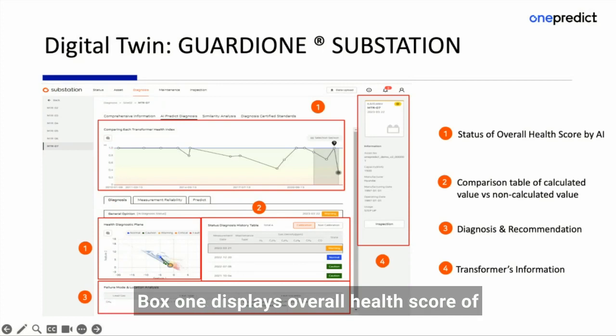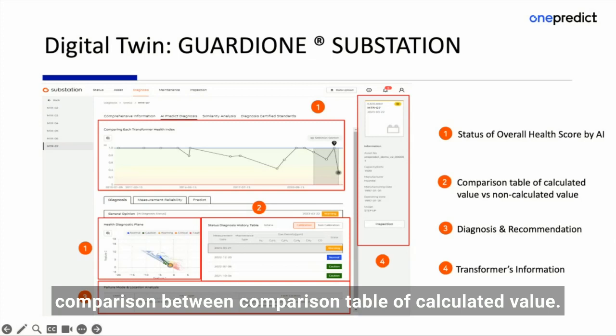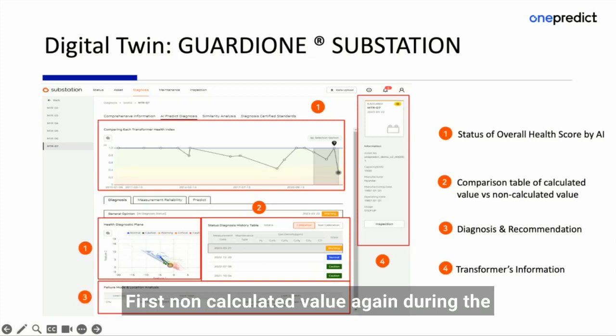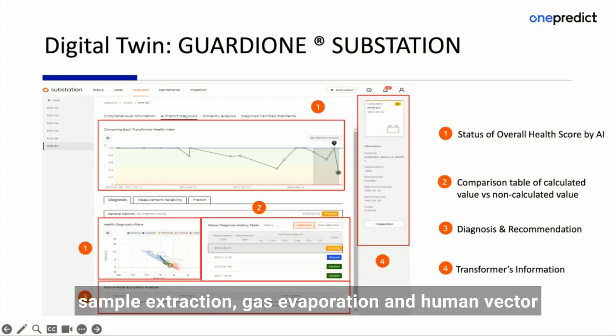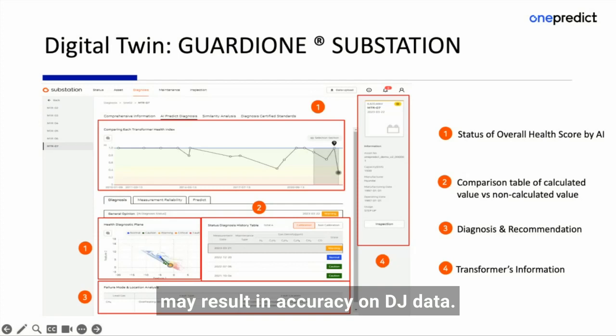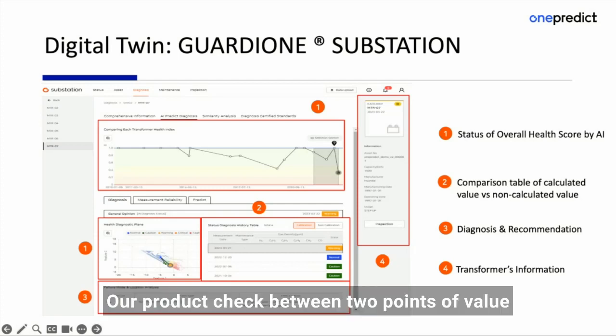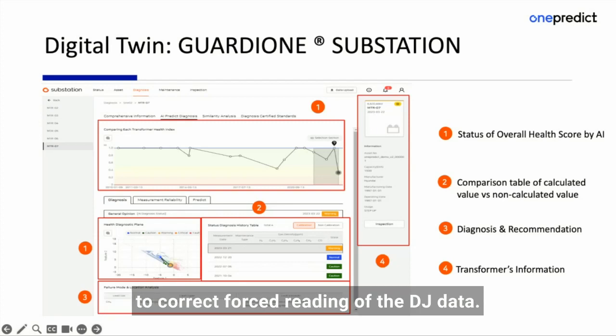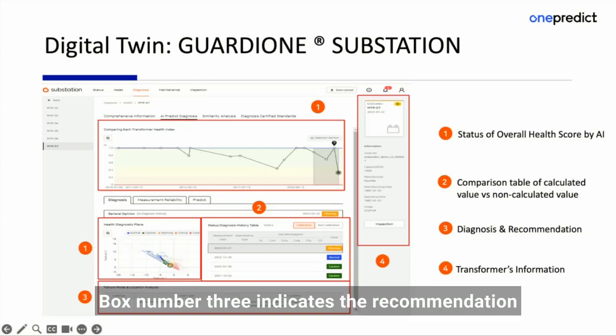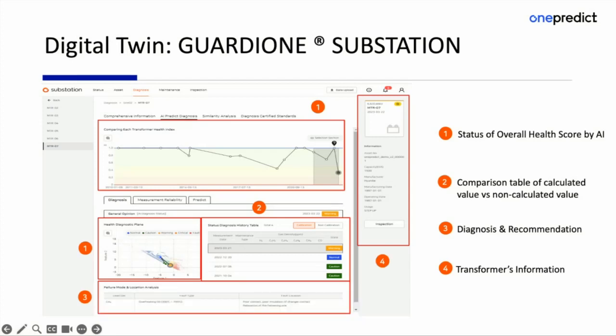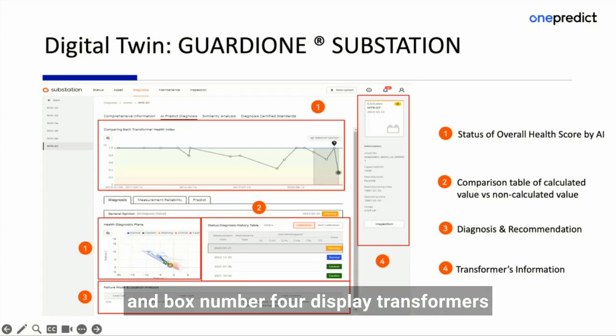On this page, box 1 displays the overall health score of the transformer by AI, and box 2 shows a comparison table of calculated value versus non-calculated value. Again, during sample extraction, gas evaporation and human factors may result in inaccuracy in the DGA data. Our product checks between two points of value to correct false readings of the DGA data. Box number 3 indicates the recommendation. And box number 4 displays transformer information.